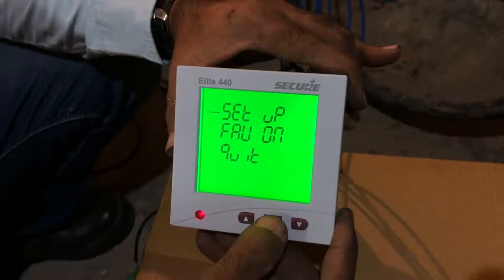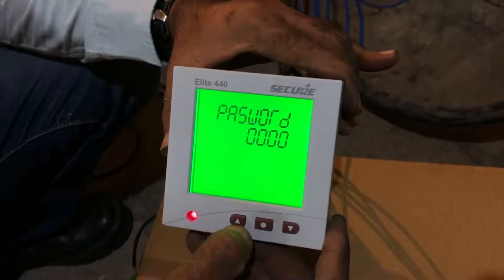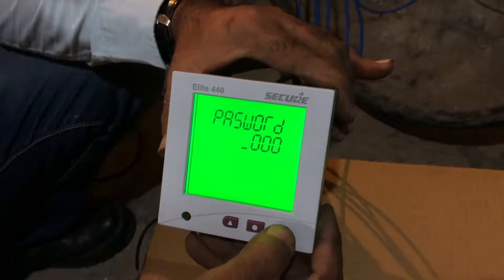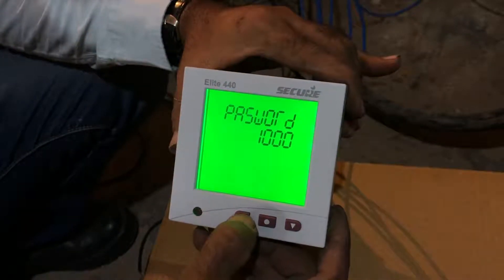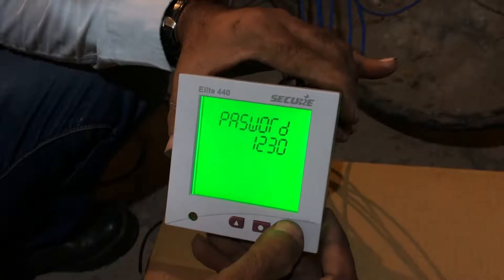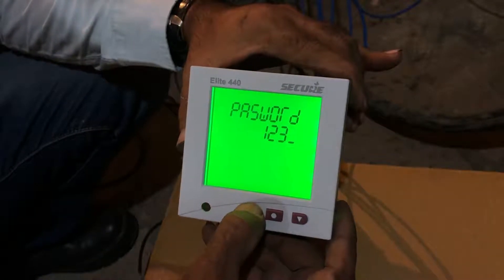Now we will see how to set up CT ratio in MFM. We'll put the password one two three four using the key functions described in the video, then we'll press enter. Now we will come onto the second part of the menu.